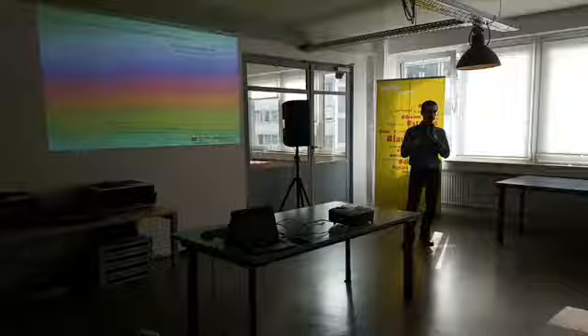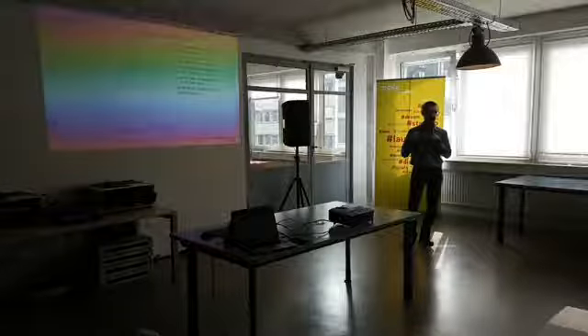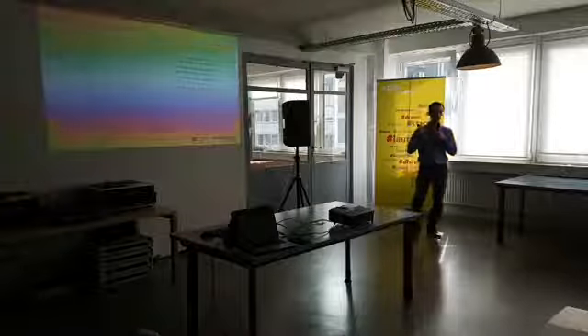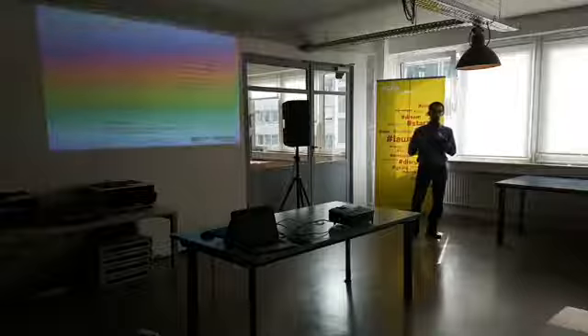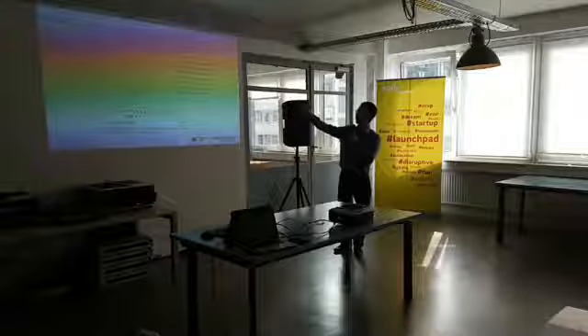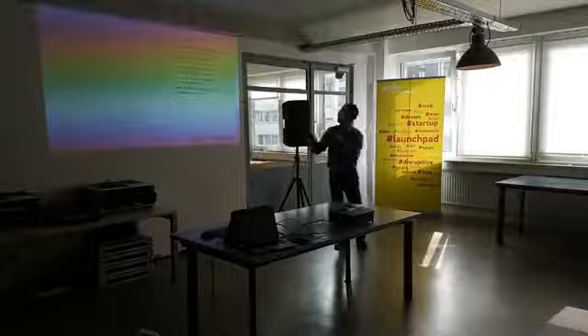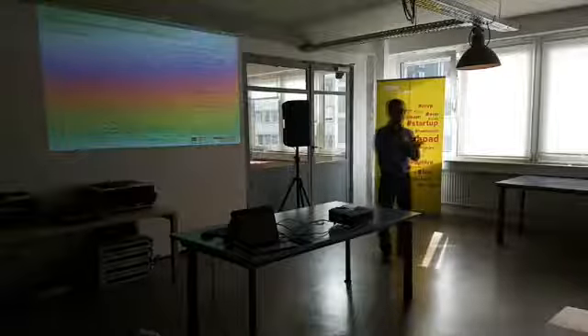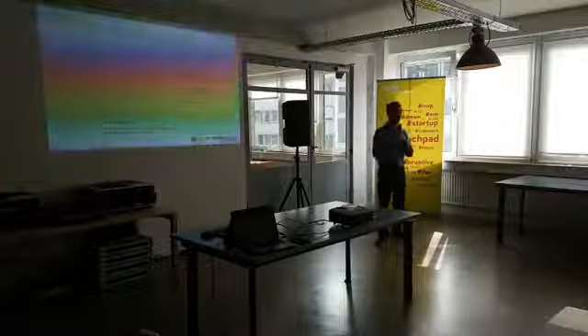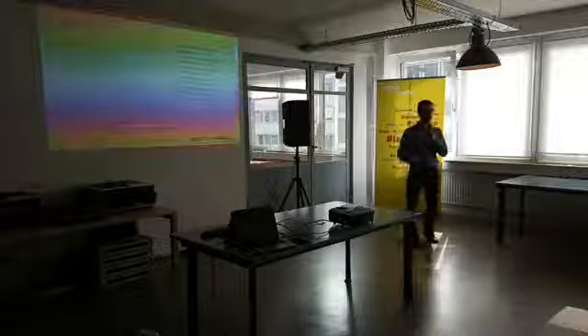Here I show just the test for the metrological characterization. To give you a quick idea, the performance of the PMU is quantified as total vector error. We measure a vector, and we want it to differ from the actual one by no more than 1%, so total vector error should be below 1%. Here I show the total vector error, and then I split it into magnitude and phase angle error. This is the test for the magnitude, so we test all the magnitudes that the PMU can acquire in the input. In all the cases, the maximum error was 0.1%, 10 times below the threshold. The same is true for the phase angle.